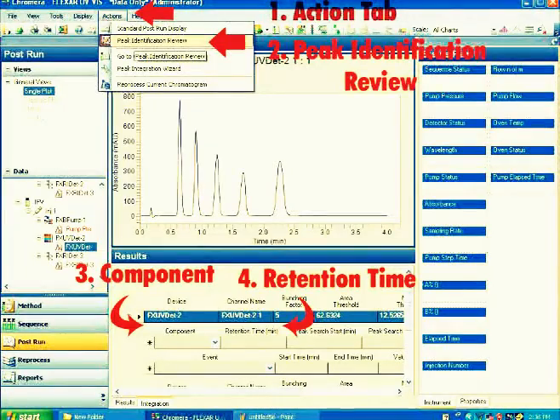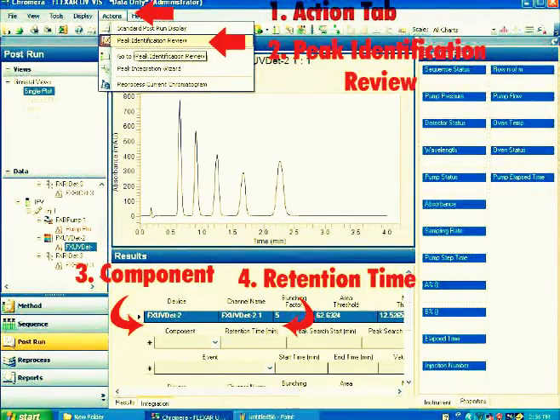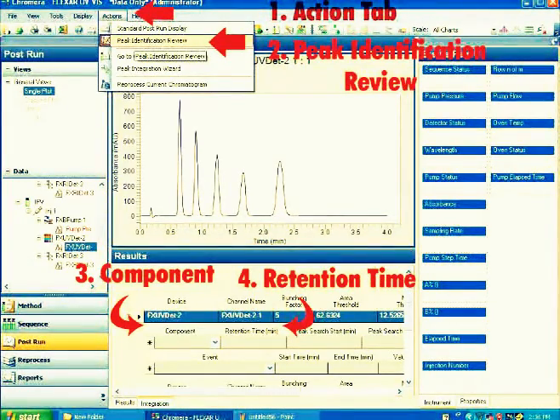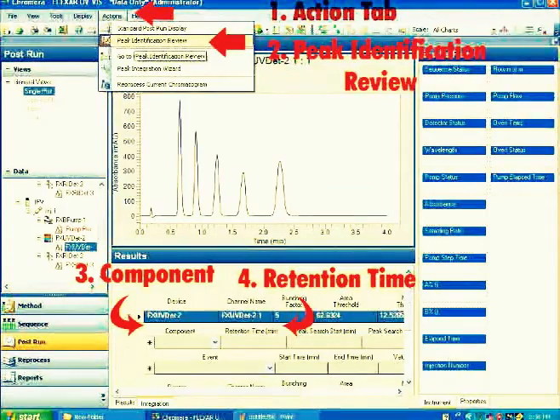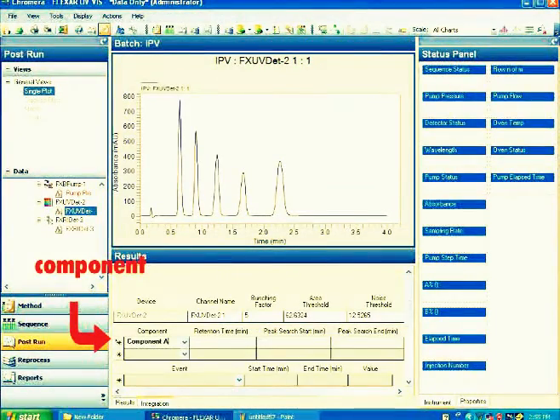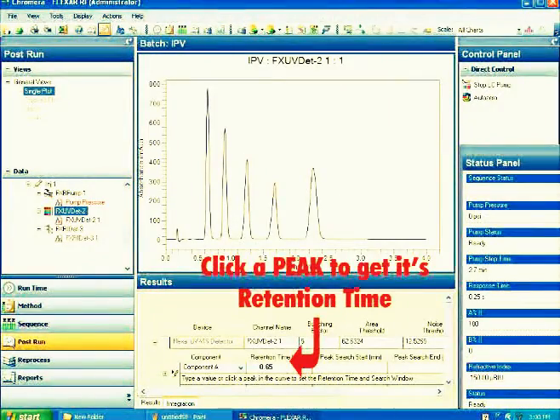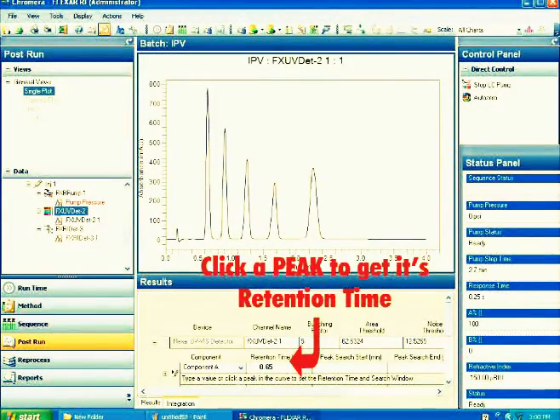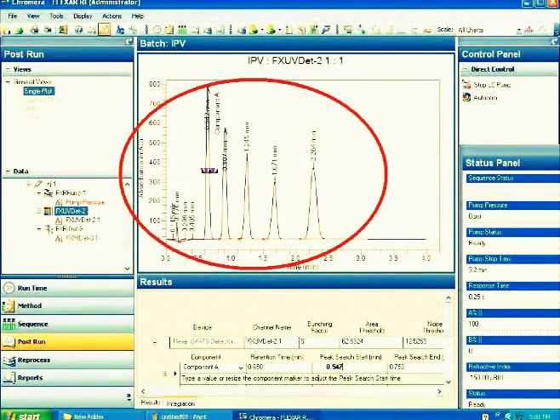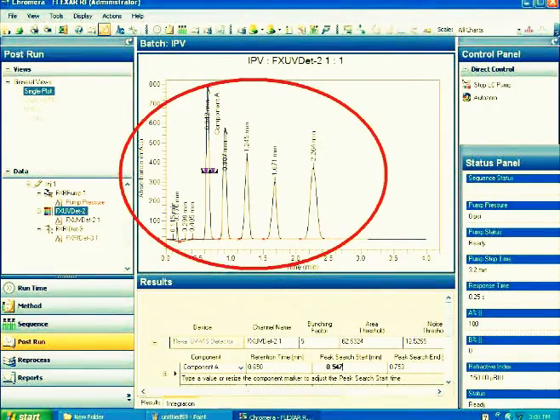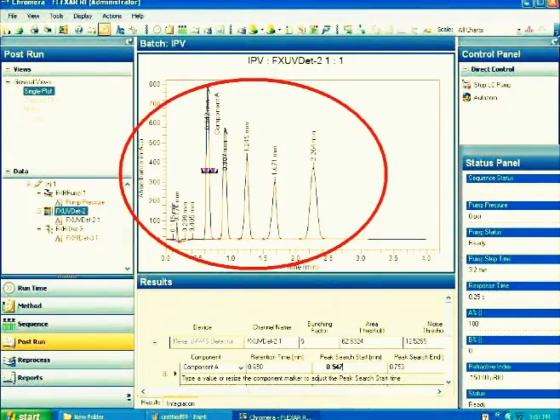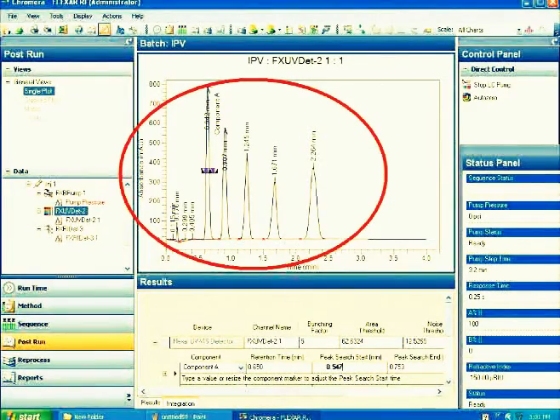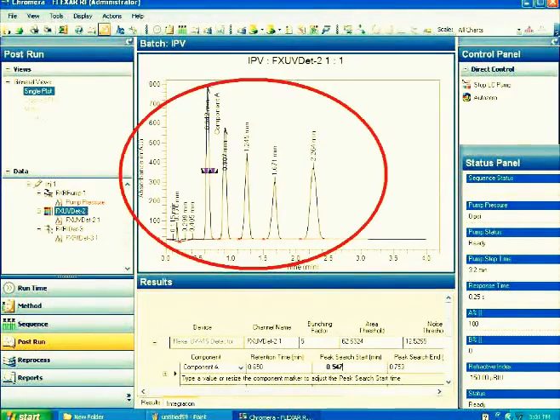We receive the data from the HPLC itself. Now we're here to identify what these peaks would represent. First, we press the action button, then go for the peak identification review. Afterwards, we input the variable name of the component. After that, we can focus or zoom into one of the peaks and identify its retention time. After getting the retention time of one of the peaks, we can easily get the retention times of the other peaks. Afterwards, it can be analyzed through comparison with standard values within the program. This would result to easily identifying which of these peaks would correspond to which specific element or compounds in the database of the program.